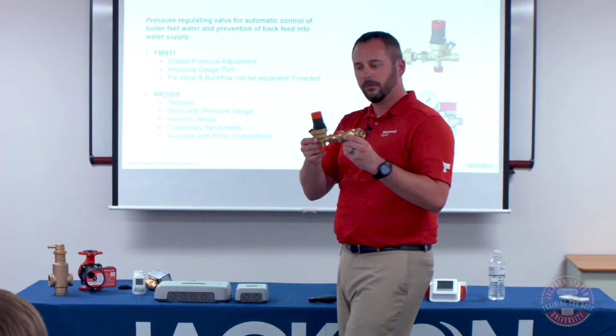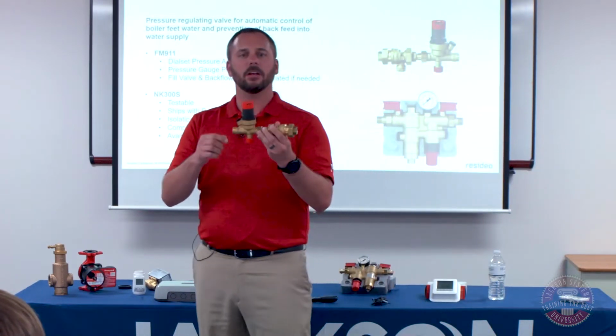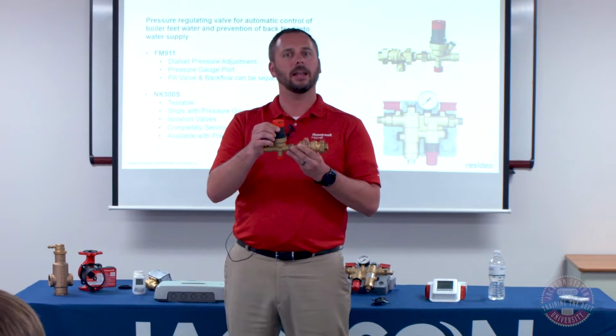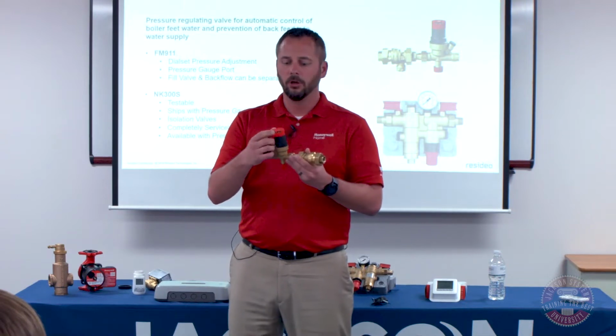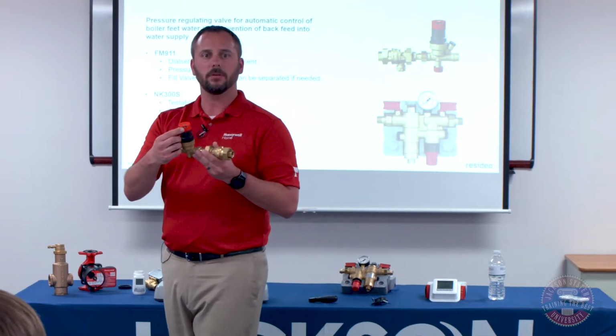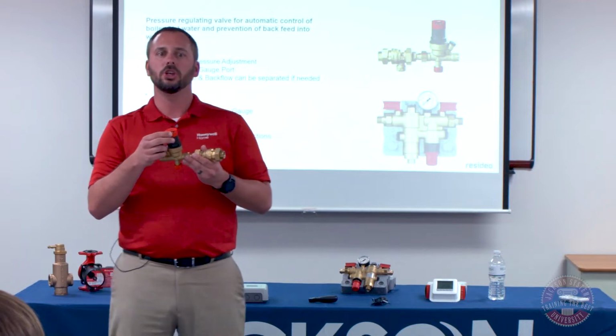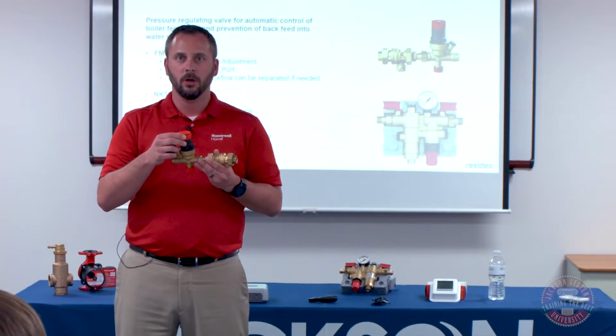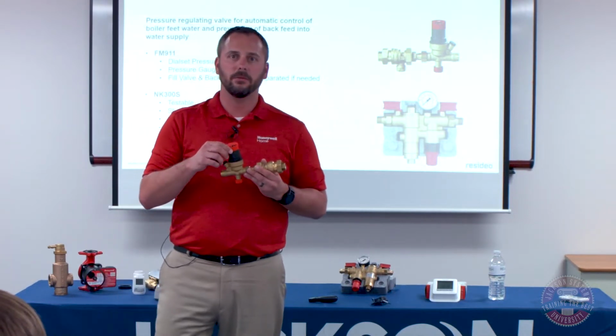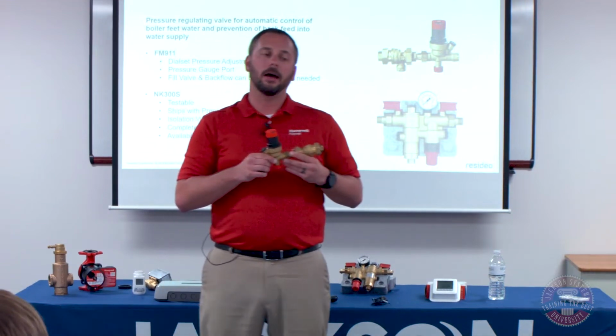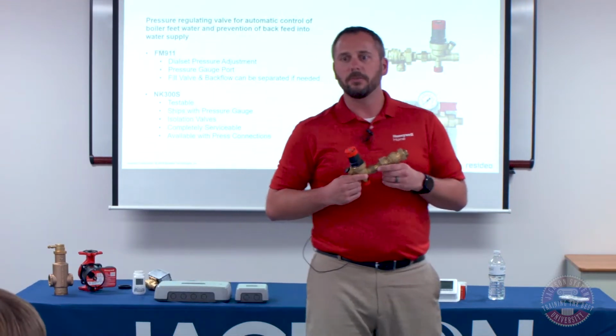Our fill valve, all of this is going to be 1/2 inch, but what we do on the top is we design it with what we call a dial set. So at the very top of our fill valve, you've got a little gauge here that's going to show you what the pressure rating is. So we come factory set at 15 psi. The old industry standard used to be 12 psi.